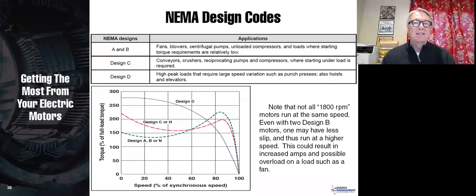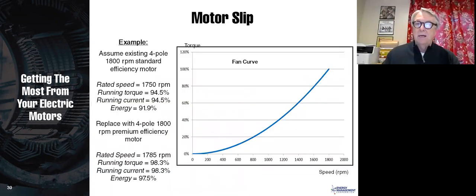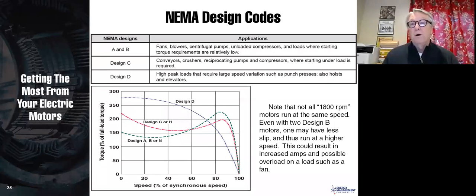There are different designs, and this is something else that can be on a motor nameplate or on a motor design sheet. You can see that the locked rotor torque, the pull-up torque, the breakdown torque, and the slip all vary considerably depending upon the design of the motor. If you have a design D motor, for instance, it's really important to replace that motor with a design D motor, because it may be there for a very good reason, in order to give you high starting torque. Or it may be there because of the slip. That's very common on walking beam pumps for oil in the oil industry. So you need to understand this.